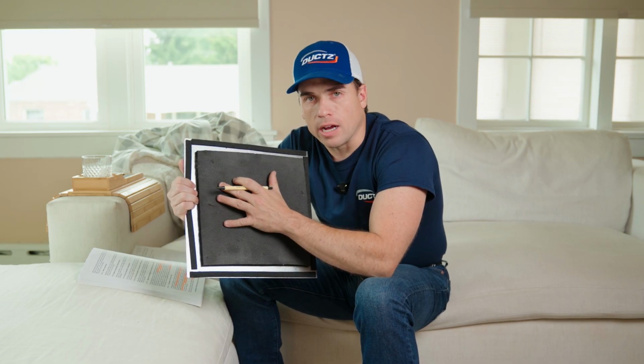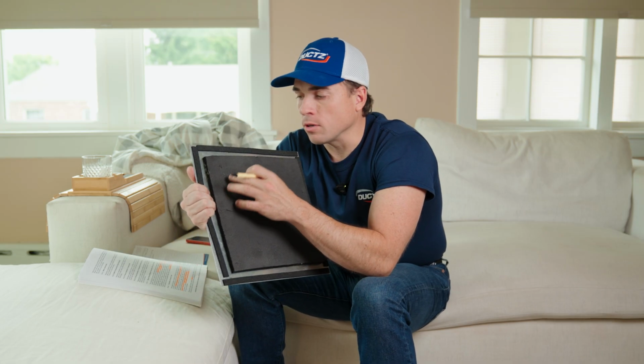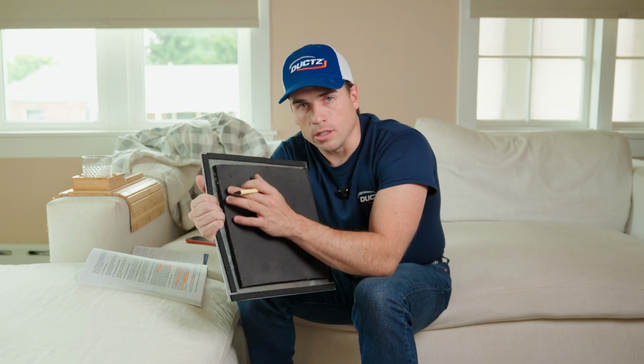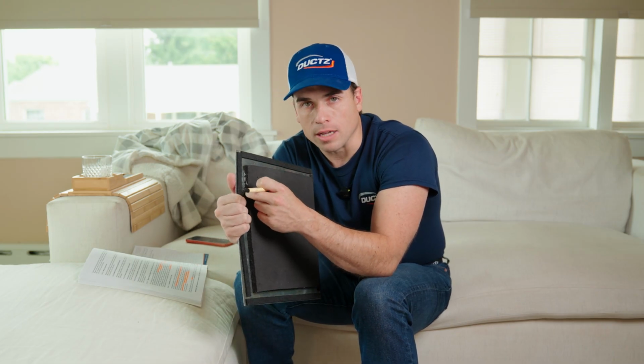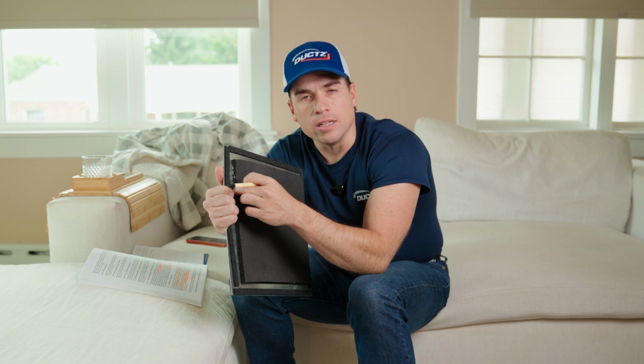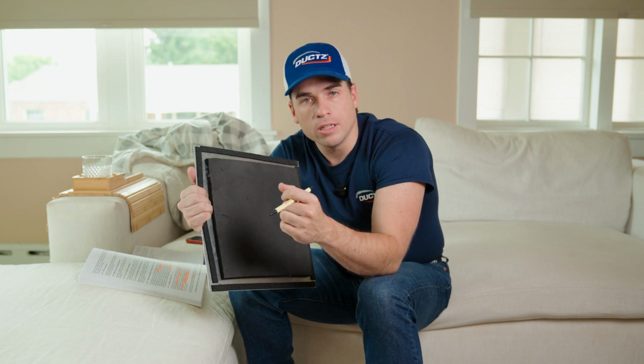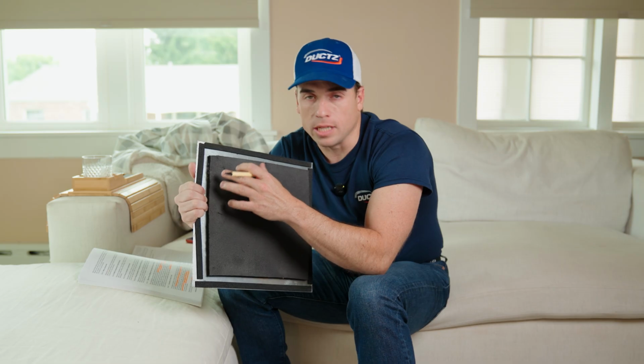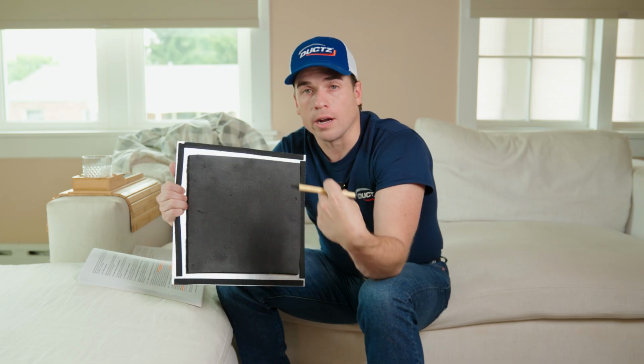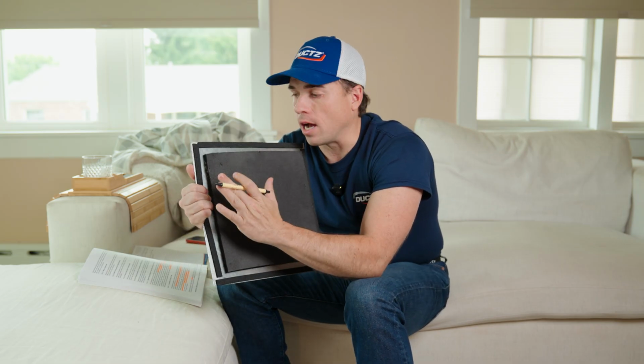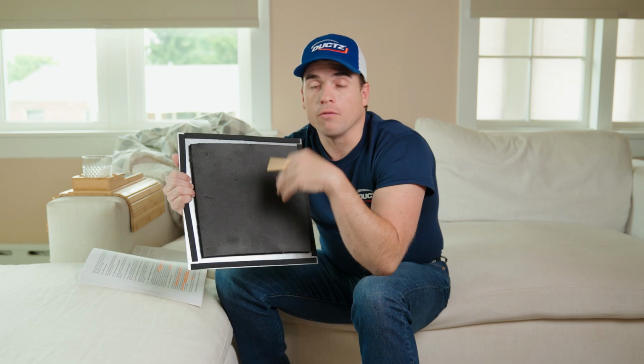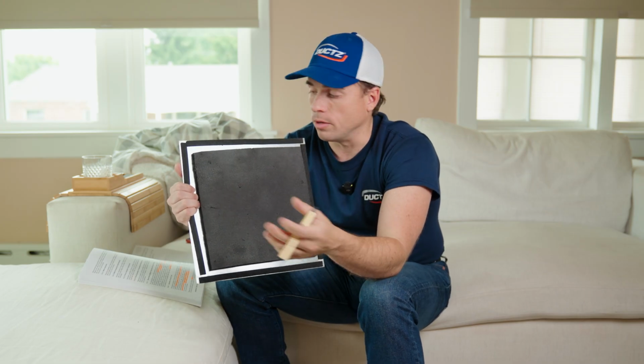you had fiberglass liner, the fiberglass is glued onto the ductwork itself, but the fiberglass liner is kind of layered, and some of those layers are already peeling. That would also fail us for the encapsulation process because the added weight would then just peel the liner off, and then half of the liner would stay glued to the duct and the other half would just fly down the duct and cause those same issues.